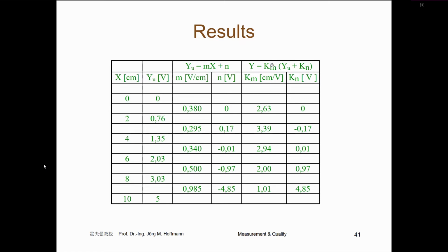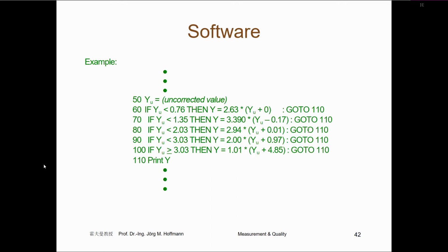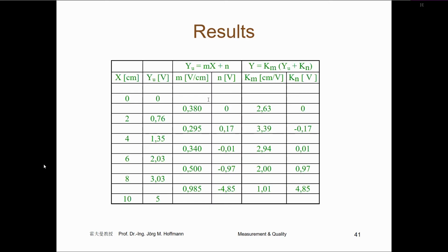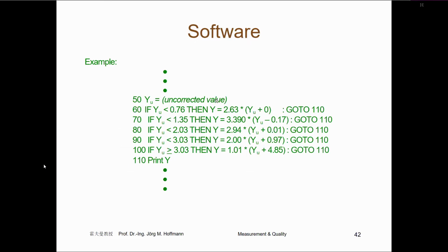For every line, you can have this formula. You read in your computer y uncorrected. You have to look in which line y uncorrected is, and then you have to use the correction function from the line where you are. And this you can do in a short program. This is a program written in BASIC or Turbo Basic. It's a very, very easy programming language. This is only the line number and you can read it. Y uncorrected is read in, the uncorrected value. That means the uncorrected value will be read into your computer.